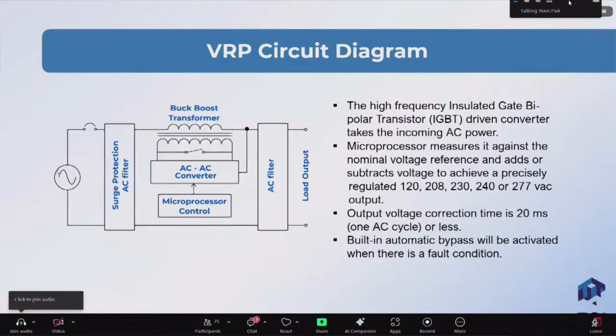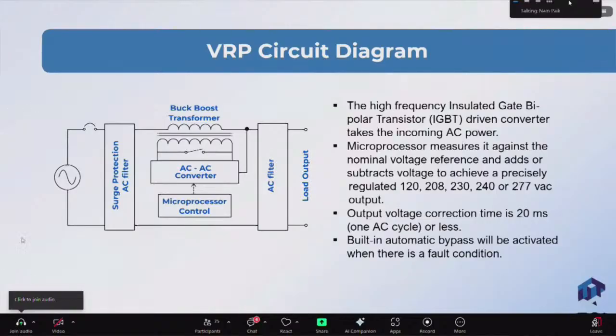You got incoming AC. This could swing, say, from 230 volts plus minus 20 or 25% in some countries, in some locations. It could also contain some surges and spikes and noise. So we first take it into our surge protector, an AC filter, primarily to protect ourselves, as well as connected equipment from surges and spikes. Sine tamer would go before this. It'll take care of all the big lightnings. You've probably seen some videos several times already of how lightning strike could damage equipment. And sine tamer surge protector will provide remnant voltage of like 400 or 500 volts, which we can handle without any problems.